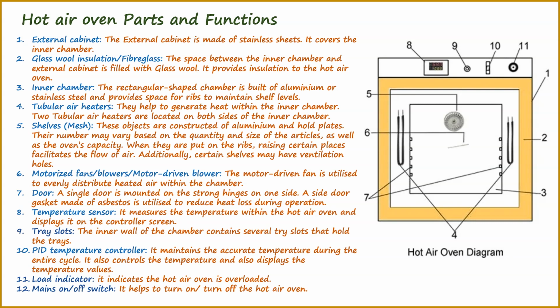The sixth part is motorized fans or blowers. The motor-driven fan is utilized to evenly distribute heated air within the chamber. The seventh part is the door. A single door is mounted on strong hinges on one side. A side door gasket made of asbestos is utilized to reduce heat loss during operation.